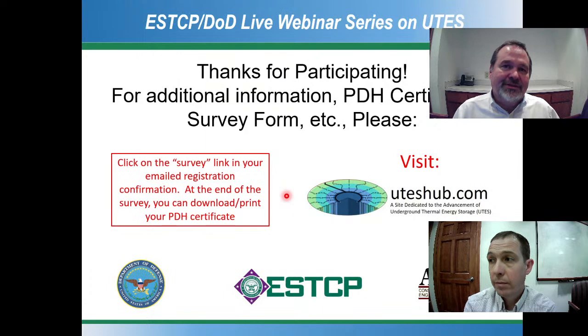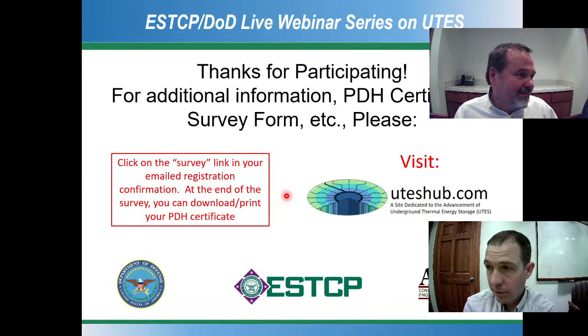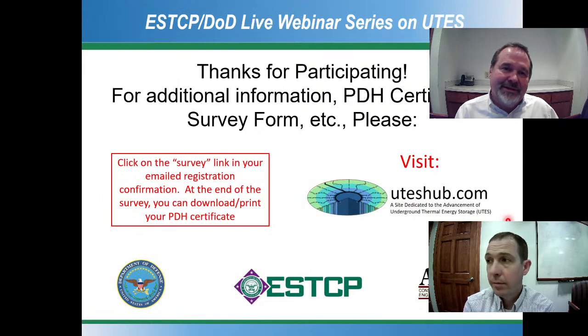But probably the smallest system we've done with BTES, Brandon, what was that, 67 boreholes maybe? I think I counted them up the other day. And what was it roughly, 75 tons? Roughly, yeah. 75 is less than 100 tons. We kind of say minimum tonnage for a geothermal system to be done BTES is probably around 75 tons. That's because you've got to buy the reversing valves. And then the other thing is obviously circuiting the boreholes is a little bit different. But the contractors we've worked with have figured that out pretty well.